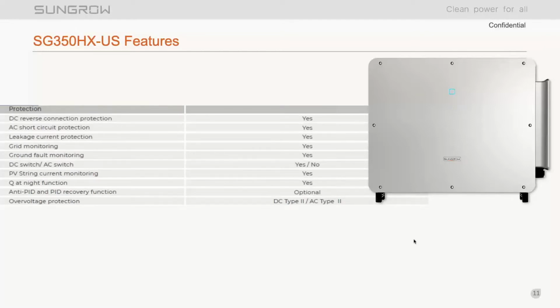As far as protections go, we do still have DC reverse connection protection, AC short circuit protection, leakage current. We have grid monitoring, of course, as well as some pretty sophisticated grid support features. We do have a DC switch, but there is no AC switch on the unit, and I'll go over that a little bit later as well.